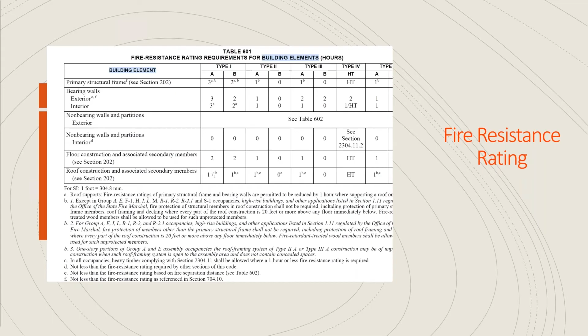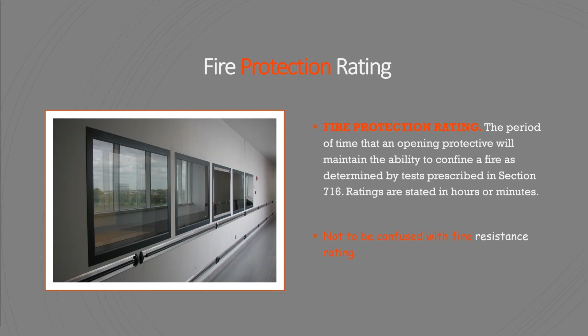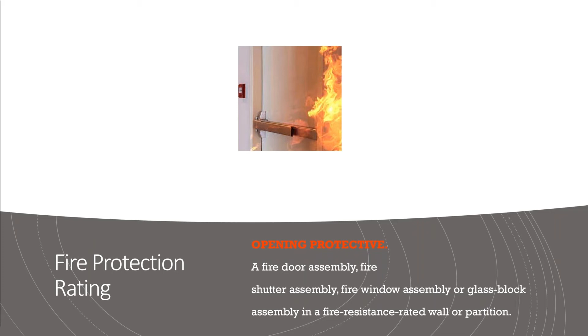And then fire protection rating is defined as the period of time that an opening protective will maintain the ability to confine a fire as determined by test prescribed in section 716. Ratings are stated in hours or minutes. So similarly noted here, not to be confused with fire resistance rating. So with fire protection rating, now we're talking about the opening protection. So what's an opening protective? It's a fire door assembly, fire shutter assembly, fire window assembly, or glass block assembly in a fire resistance rated wall or partition. So again, don't confuse the two. Yep, both require a level of protection, but they're 2 different things, and the way that those are protected and the tests that those have to meet are different.